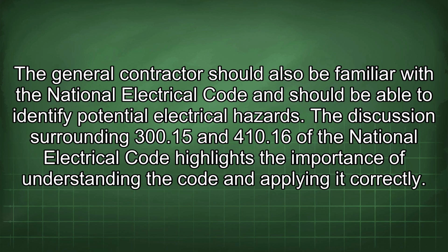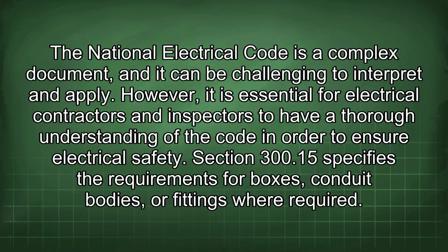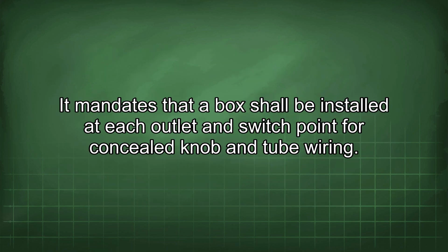and applying it correctly. The National Electrical Code is a complex document, and it can be challenging to interpret and apply. However, it is essential for electrical contractors and inspectors to have a thorough understanding of the code in order to ensure electrical safety. Section 300.15 specifies the requirements for boxes, conduit bodies, or fittings where required. It mandates that a box shall be installed at each outlet or switch point for concealed knob and tube wiring.